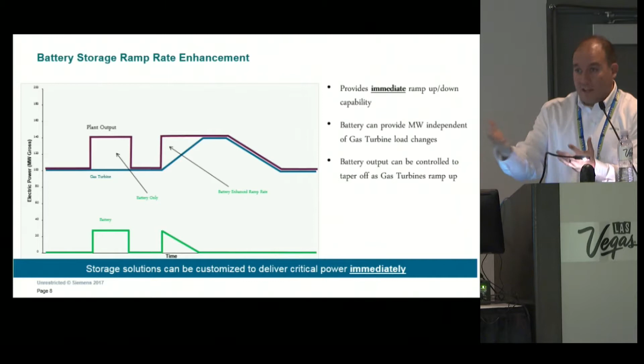Okay. One other example for batteries, for a combined cycle plant, this is immediate firming capacity with a high efficiency combined cycle. So again, x-axis is time, y-axis is output. Now in this particular example, at time 0, an event happens on the grid. And an event can be anything. The loss of a major generation unit, the sun goes behind the clouds, the wind stops blowing. Whatever it is, it's requiring the grid to say, I need output from your plant right now. In this particular example, this delivers 78 megawatts in 250 milliseconds to the grid, and then delivers that 78 megawatts for as long as the grid needs it.